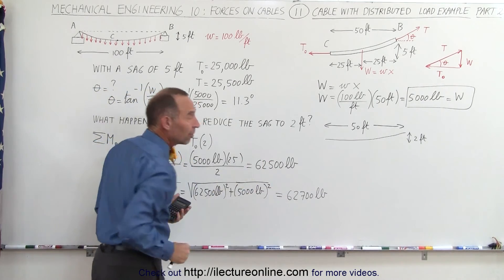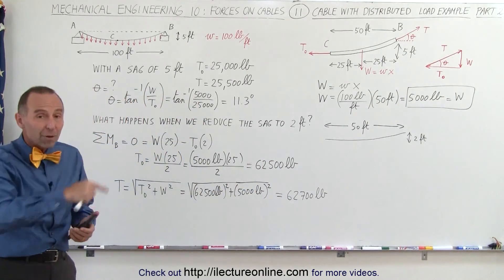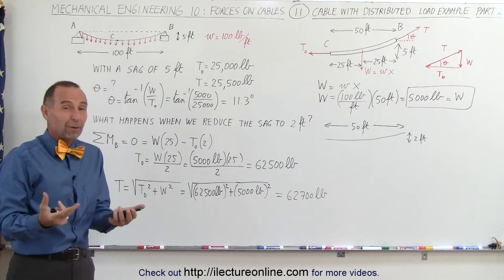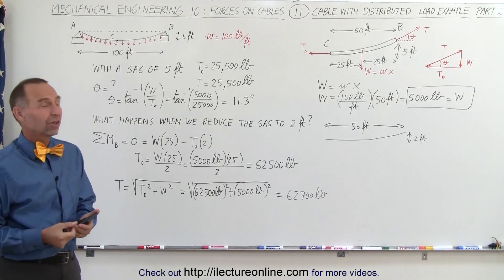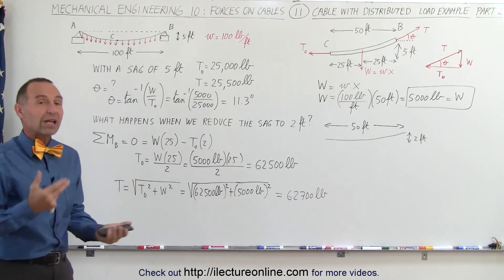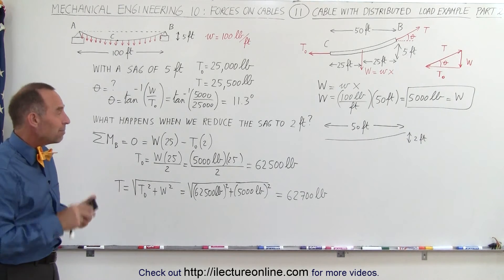Because when you do, then of course you increase the tension by a tremendous amount. If you have too much of a sag, then of course you lengthen the length of the cable, and with power cables you would have more resistance and it would be more expensive because you would need more cable.